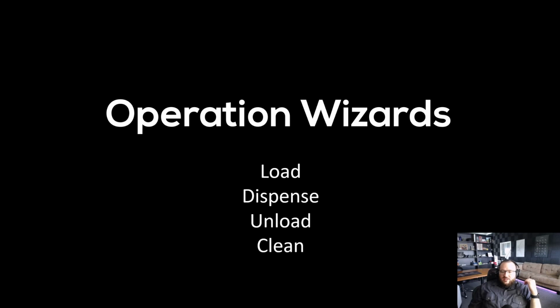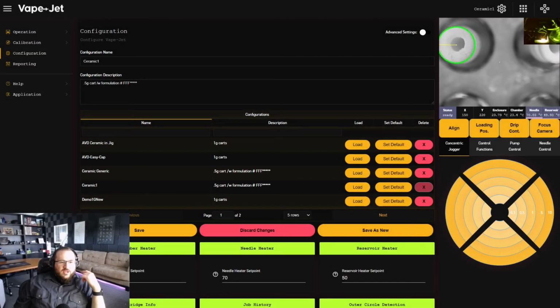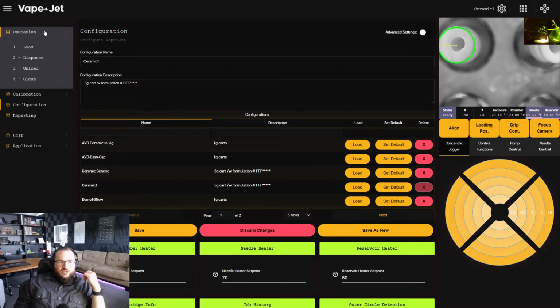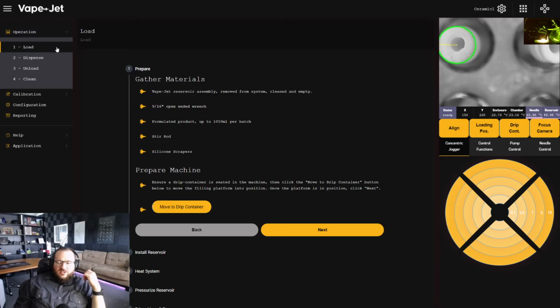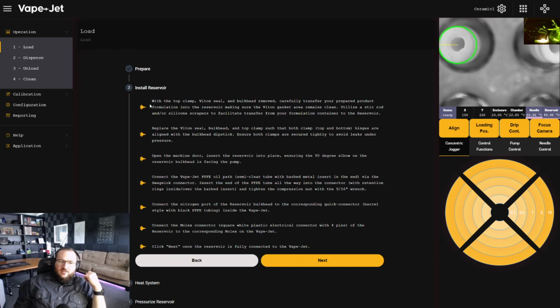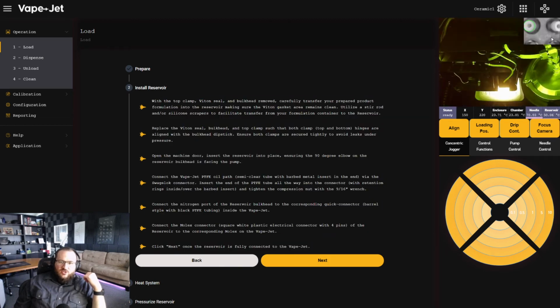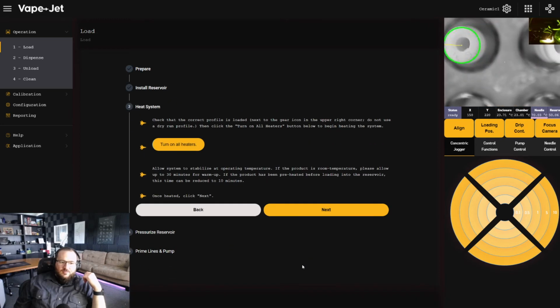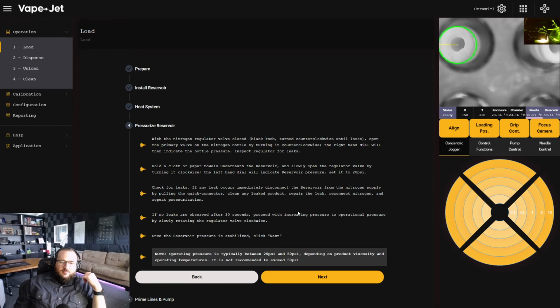Now all the wizards in this machine are set up with the SOPs built in. So we're going to go to Operation, Load. And what you're going to notice is every time you do an operation with the VapeJet system, you're going to be presented with the SOP. Furthermore, any buttons that the operator needs to click are included inside the wizard here. So it tells you what you need, what you're going to do, and then brings the button right to you. So next, it walks you through what you need to do to install this reservoir here inside the system. It tells you that you need to heat it up. It tells you that you need to pressurize it. It walks you through how to pressurize it.